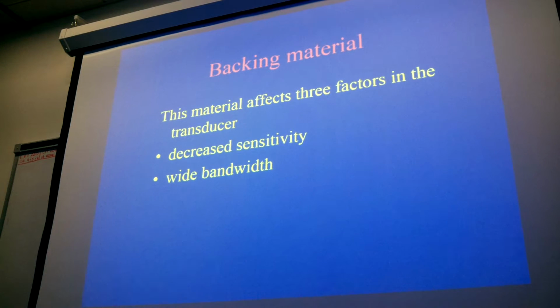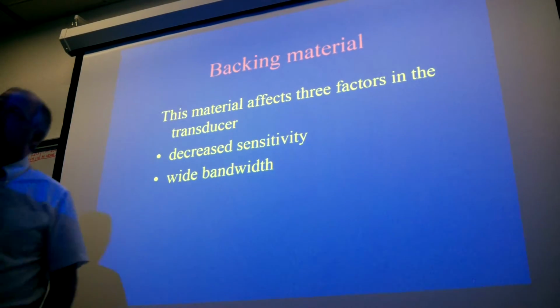So your bandwidth may be anywhere from, let's just pick it up. What does it say? 1 to 5 megahertz. That's the bandwidth. As to where one of those probes will be 5 megahertz only. This one will transmit at 1 to 5 megahertz by selecting the dial on here. When they talk about in the book, they switch it when they talk about the range of.